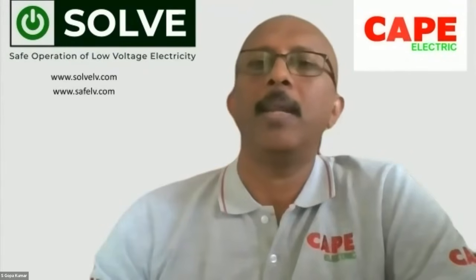Thank you. Nikhil Jain is asking, can we recommend a lightning arrestor in a storage shed where cotton fiber is stored and no electrical fittings are there? Actually, this is not related to our subject, but anyway, of course, if there is cotton or some material, for example, in the northern part of Chennai, 2 years back, there was a lightning strike, and the entire shed where the tobacco was stored caught fire. There was no electrical installation. Of course, if you don't have lightning protection and equipotential bonding, lightning will create a spark over inside the building, which can ignite a fire in other materials, which is a disaster.